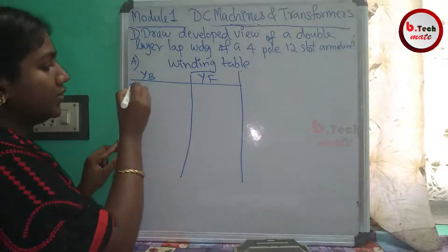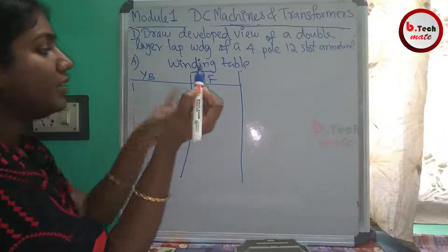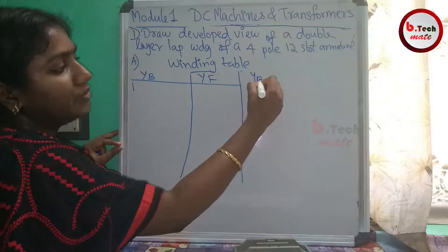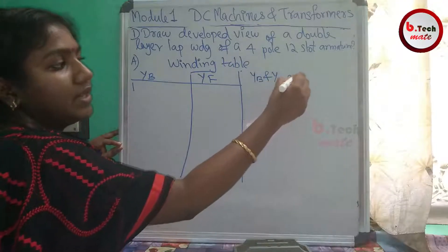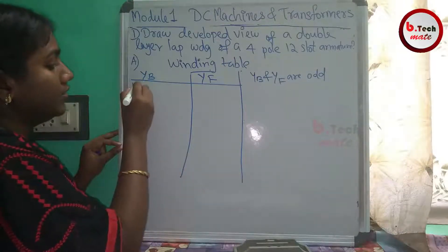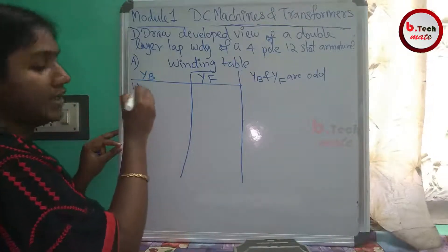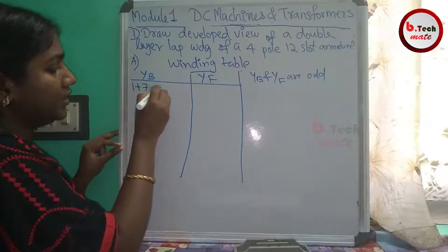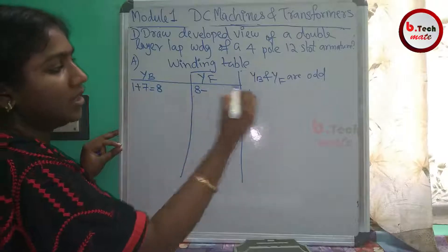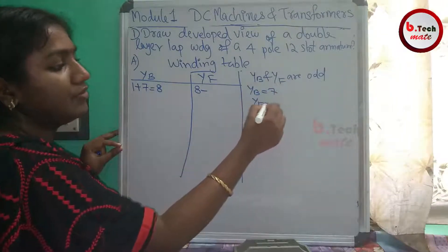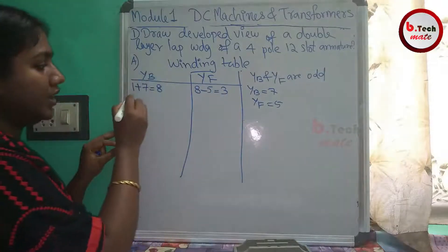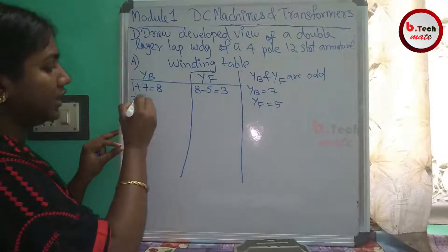YB = Z/P + 1 = 24/4 + 1 = 7. So YB = 7. YF = YB − 2 = 7 − 2 = 5. We start with conductor 1. Using YB: 1 + 7 = 8. Using YF: 8 − 5 = 3.